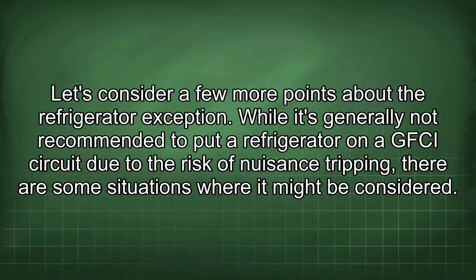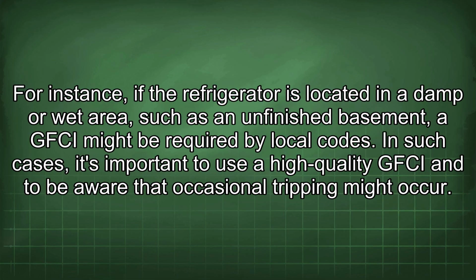Let's consider a few more points about the refrigerator exception. While it's generally not recommended to put a refrigerator on a GFCI circuit due to the risk of nuisance tripping, there are some situations where it might be considered. For instance, if the refrigerator is located in a damp or wet area, such as an unfinished basement, a GFCI might be required by local codes. In such cases, it's important to use a high-quality GFCI and to be aware that occasional tripping might occur.